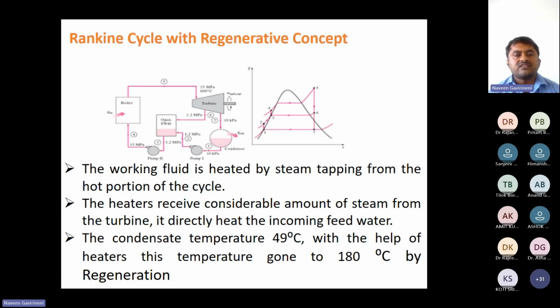After the deaerator, there is a feed pump arrangement. That feed pump supplies the water to the boiler through the HP heater. So there are two streams here: one is the condensate stream and the other is the feed water stream. For the condensate stream we use LP heaters, whereas for the feed water stream we use HP heaters. And the LP heater acts as a heat exchanger only.